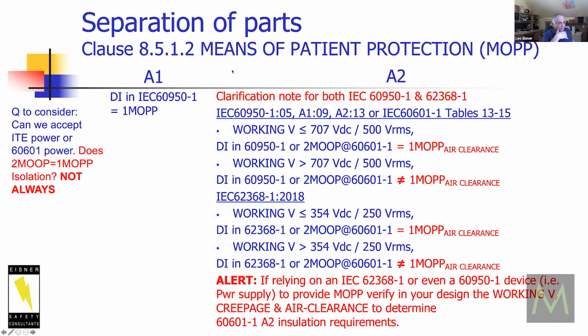So we talked about means of separation of parts. In Amendment 1, we used to allow in 60950 2 means of operator protection equivalent to 1 means of patient protection. You're not going to be able to do that anymore because of the voltage level requirements, which go higher than a certain voltage for 60950, and it's about half for 62368. So we highly recommend using 60601-1 power supplies for 601 testing and 1-2 testing especially. And for those, just in layman's terms, that is 2 MOOPs do not always mean 1 MOPP.